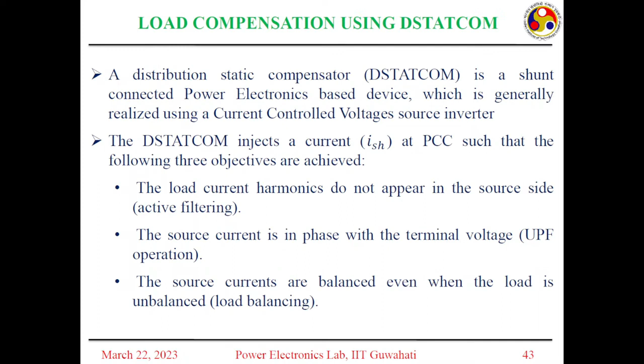So we can see the schematic diagram of a DSTATCOM here. This is only a single phase system, and we can basically extend it to the three phase system. Generally DSTATCOM is used in three phase systems only; for representative purposes this is drawn as a single phase system. Now you can see this is called the PCC, point of common coupling, where you have a common connection to the feeder, the load and the DSTATCOM.